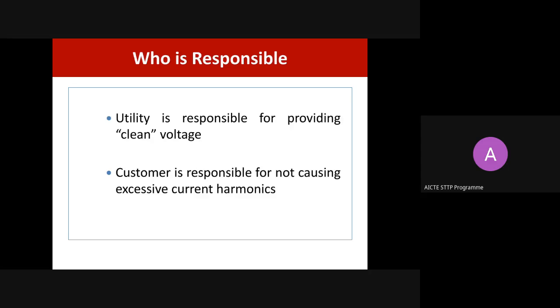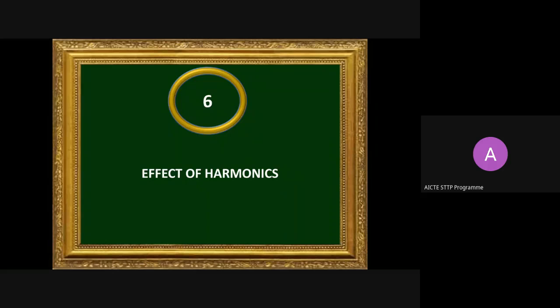For that purpose, the utility is insisting that all customers put appropriate filters in the customer premises to filter out all the current harmonics. Thereby, these harmonics should not reflect into the point of common coupling, which has an impact on the voltage of the system. So the utility is responsible for providing clean voltage. Excessive current harmonics should be blocked by the customers. The customer is responsible for providing appropriate filters in their premises to block all the harmonics, so that they do not impact the point of common coupling, which affects the voltage.